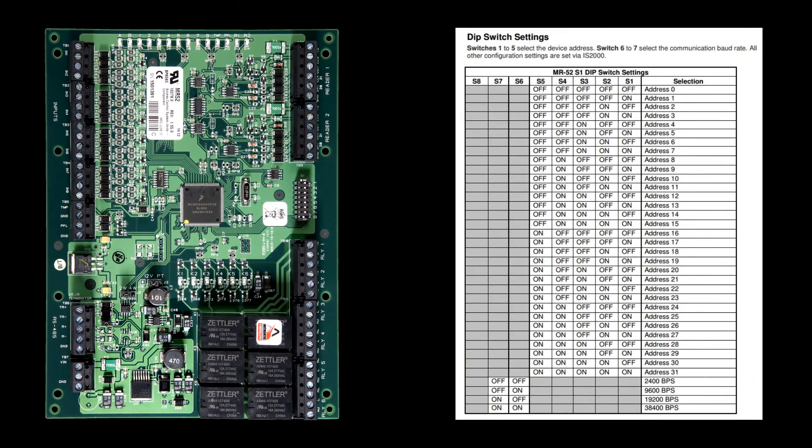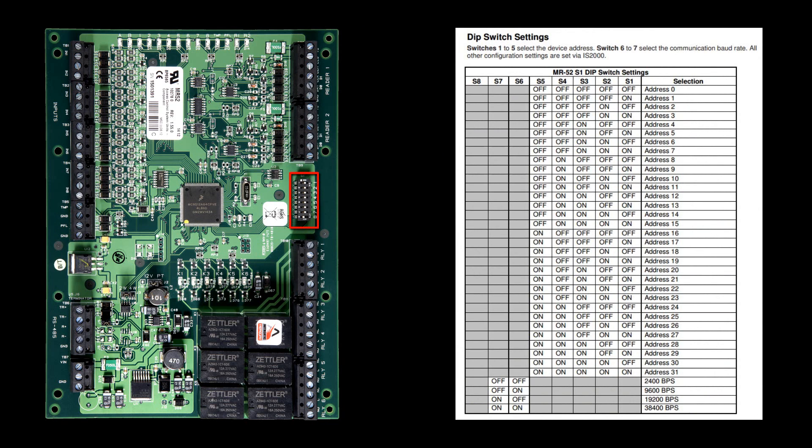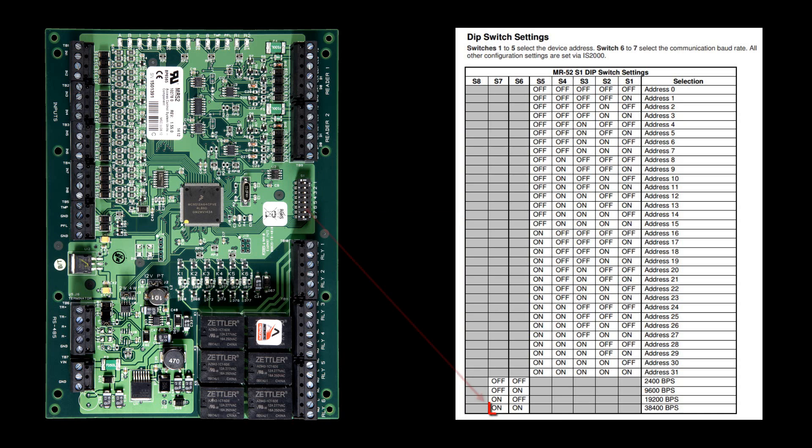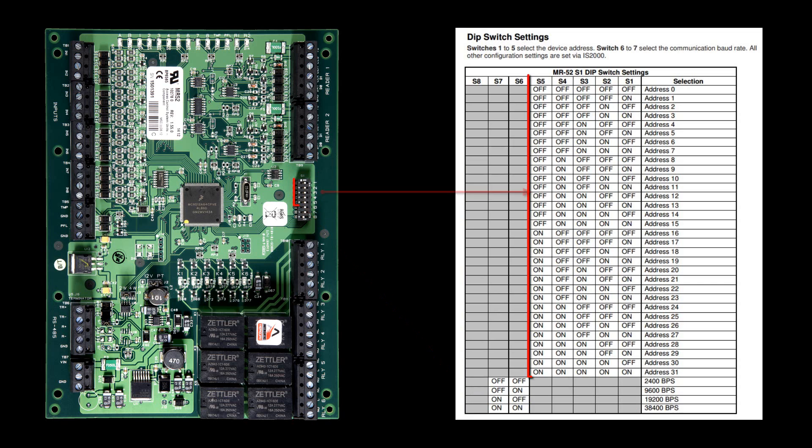The MR52 addressing is done from the DIP switches located on the panel. DIP switch 8 has to be in the OFF position for normal operation. DIP switches 6 and 7 are used for the baud rate. Default Genetech baud rate is 38,400. So both DIP switches have to be in the ON position.